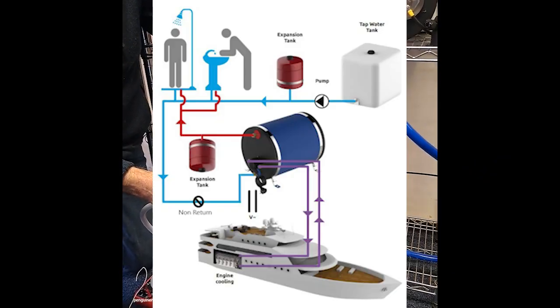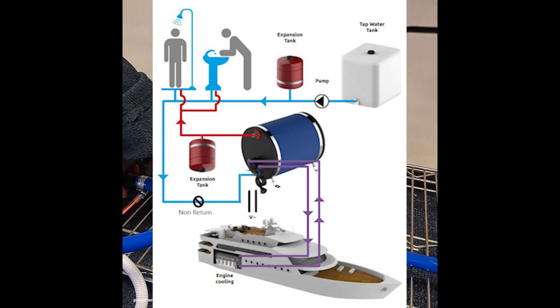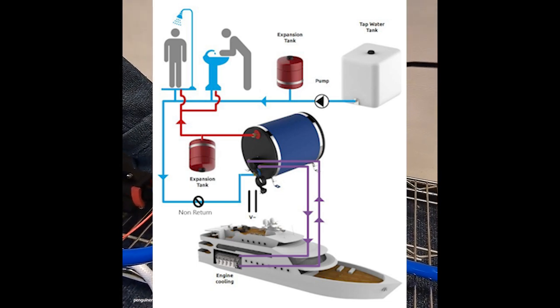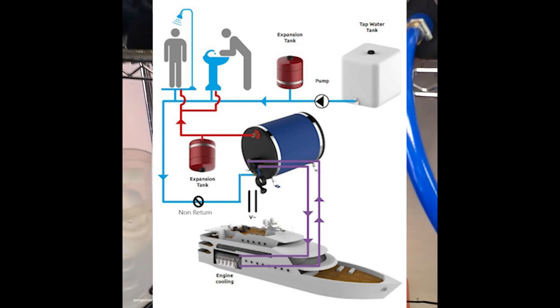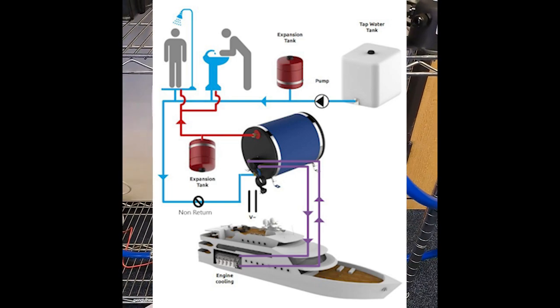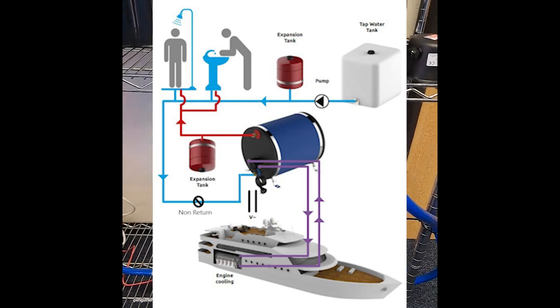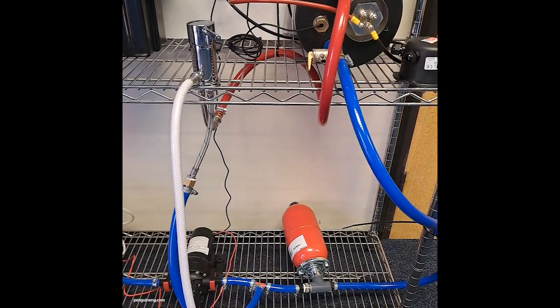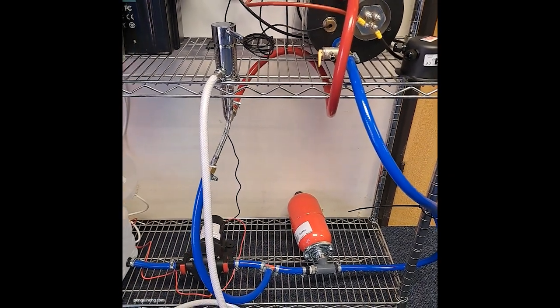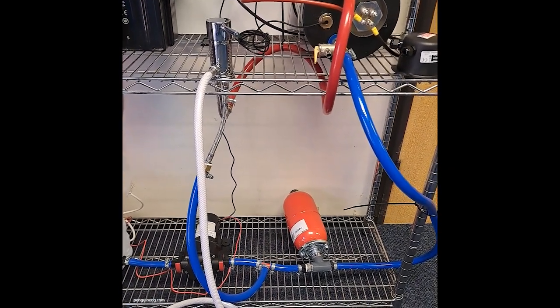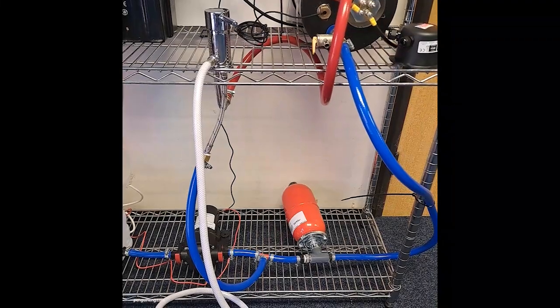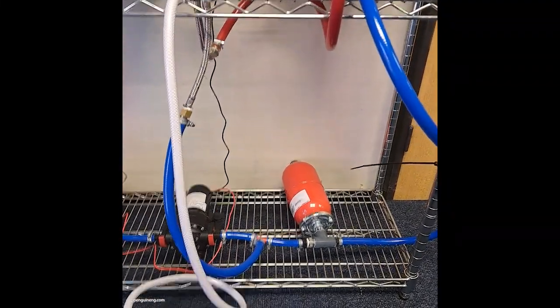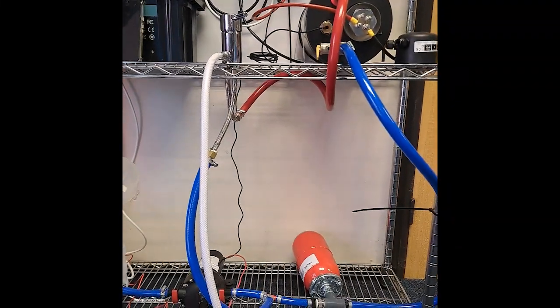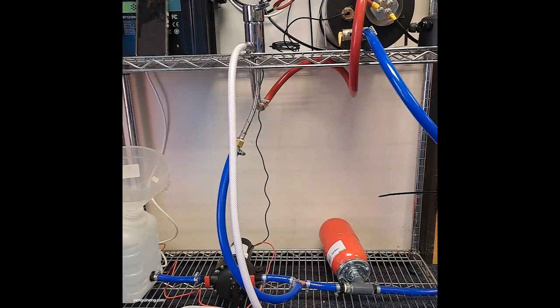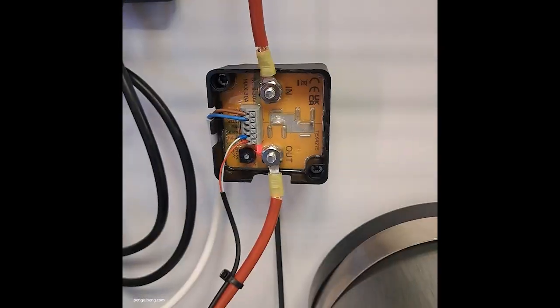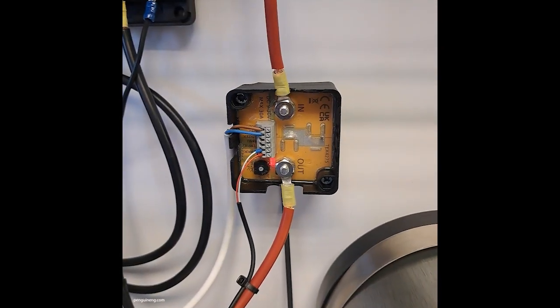The belt and braces solution is to have 2 accumulators, one each side of the non-return valve. On the cold side, it will reduce the pulsing. On the hot side, it will protect your pipework against expansion. It will also stop warm water from entering the cold water circuit, with possible risks of contamination. That said, a great many boats are built without a non-return valve and only one accumulator in the system. Whichever way you decide to go, make sure you fit one on the hot side as a minimum.